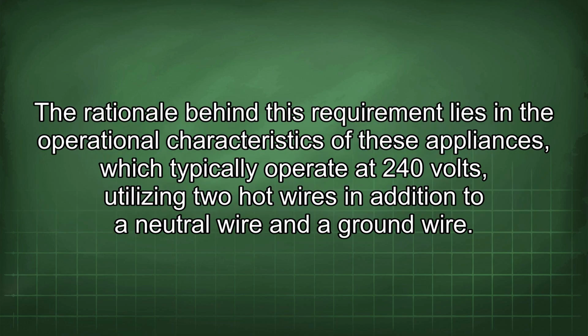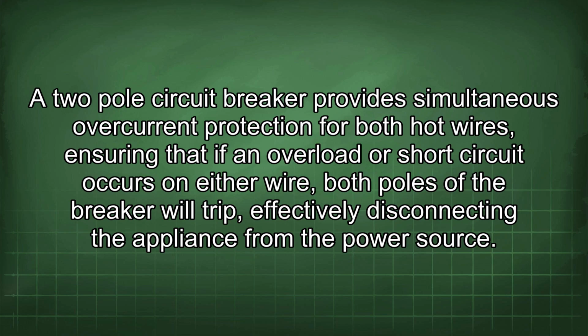The rationale behind this requirement lies in the operational characteristics of these appliances, which typically operate at 240 volts, utilizing two hot wires in addition to a neutral wire and a ground wire. A two-pole circuit breaker provides simultaneous overcurrent protection for both hot wires, ensuring that if an overload or short circuit occurs on either wire, both poles of the breaker will trip, effectively disconnecting the appliance from the power source.